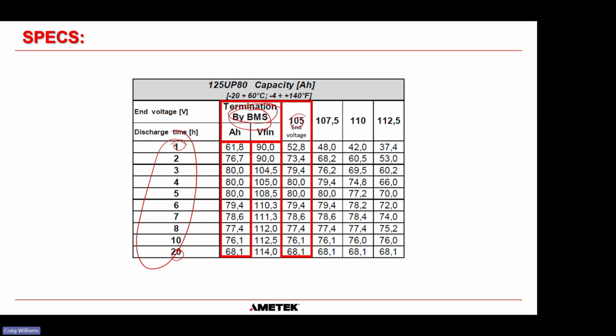So what they're saying is, if you're doing a 1 hour discharge, you will get 61.8 ampere hours, not the 80 ampere hours that it's saying, and its end voltage will be 90 volts, and the BMS will terminate the discharge at that point. Okay. But the salt batteries work really well in this 3, 4, 5 hour range. And you can see that they're saying that you will get 80 ampere hours, okay, down to a voltage of roughly 105 volts at that range there.